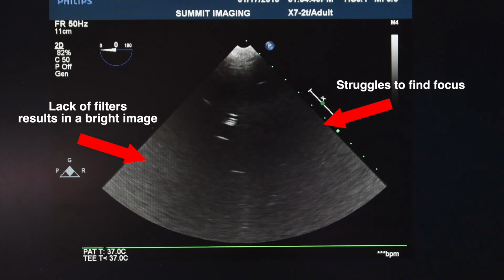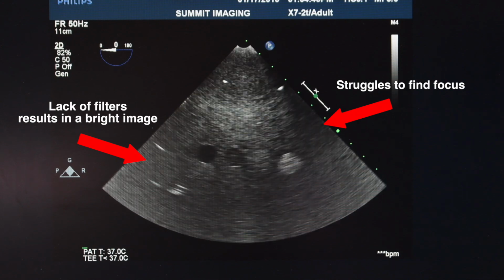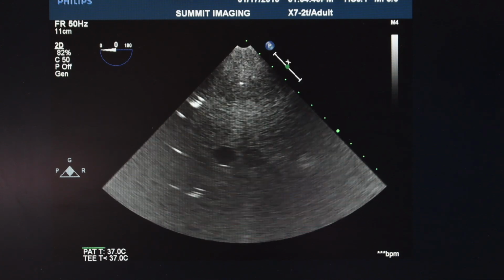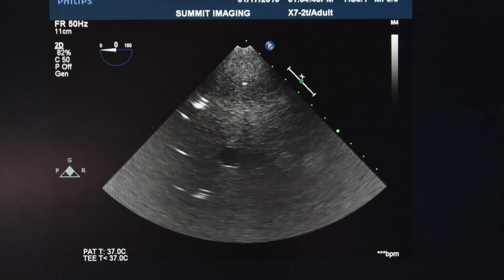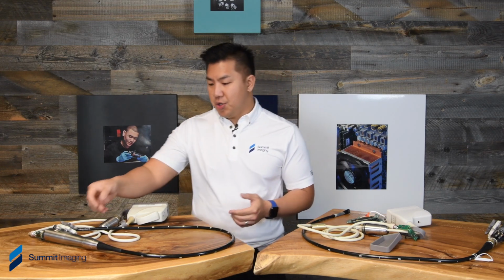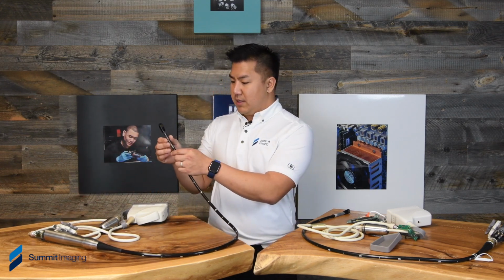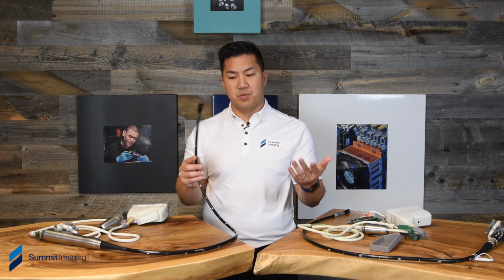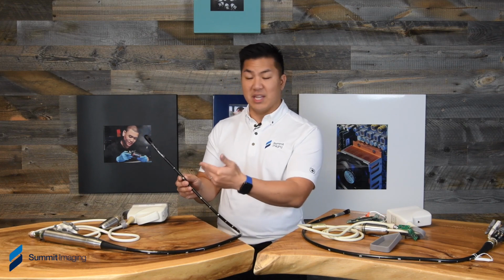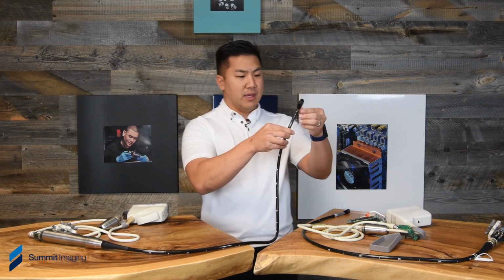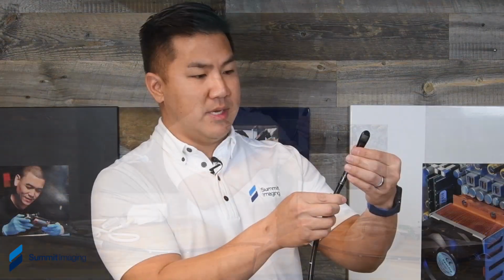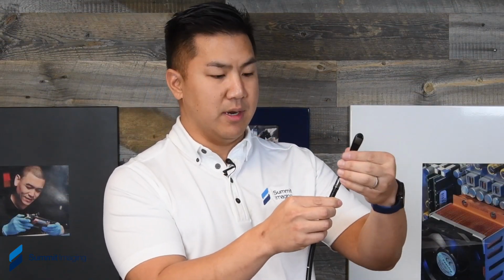We haven't pulled back the lens to fully assess because the customer wanted us to keep that intact for right now for their own educational purposes internally. But that is an issue that you can see on the screen now. The final thing we wanted to show you is that in assessing and evaluating this transducer, with the customer's permission to disassemble it to the level that we have, if you look at this, the top portion of this TEE probe, the head and the bending section here, should be properly attached to this insertion tube.